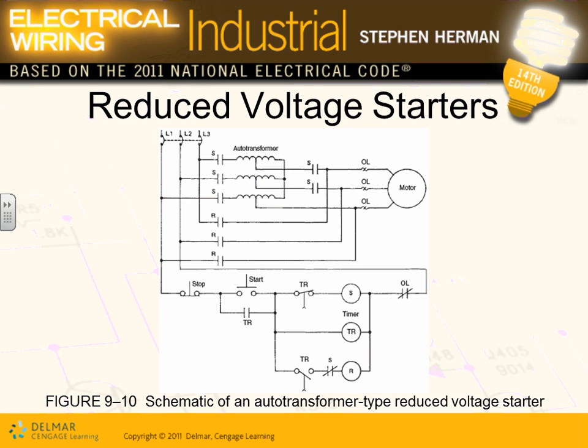The only thing you need is probably for safety, because right now, if you leave it as is, when this is energized, there will be a voltage sitting right here. But this is inside the controller. There's tons of voltages anyway. Yeah, it's not needed for the control system, but from a safety point of view, probably. But if it's inside the controller, you open the controller and the motor is running, you're exposed to a lot of hot stuff. Any comments, guys?